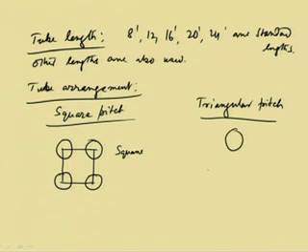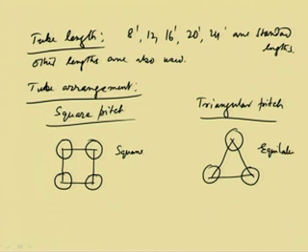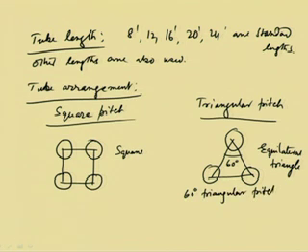Okay, and for the triangular pitch, if the center to center distances are joined, it gives an equilateral triangle. Usually these angles are 60 degree, and 60 degree triangular pitch is very common, sometimes also called 60 degree triangular pitch. We can see that the center to center distance is called the pitch, PT, square pitch, and this portion is nothing but the clearance, C. C is clearance.